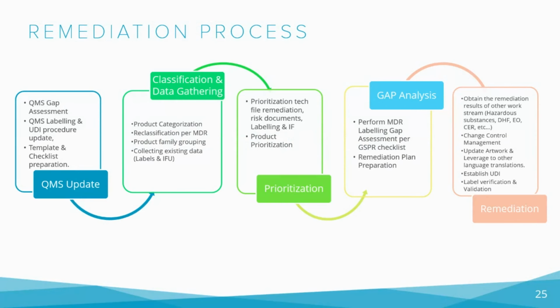This may involve updating the labeling to include the UDI, adding or revising warnings or precautions, and updating the language to make it easier to understand. The labeling remediation process can be time consuming and complex, particularly for manufacturers who have a large number of active devices on the market. However, it is essential for ensuring compliance with the EU MDR and for maintaining patient safety.